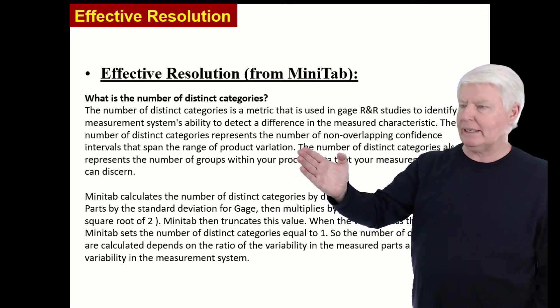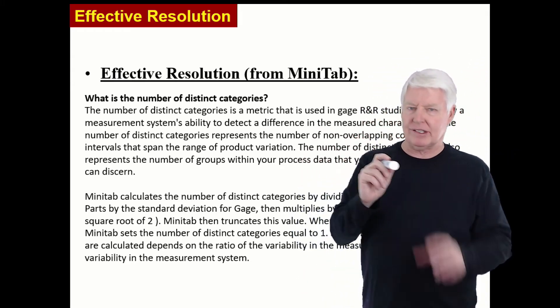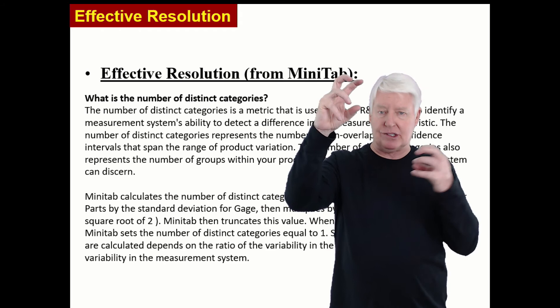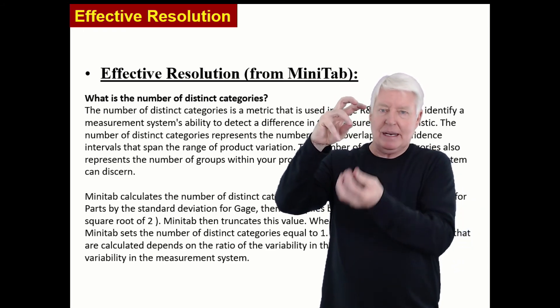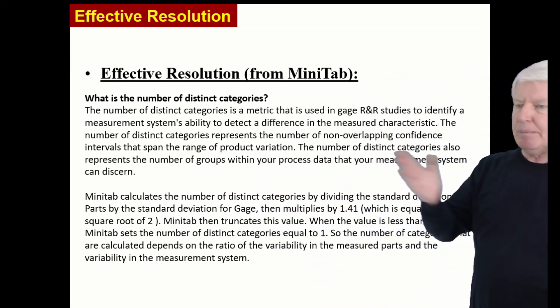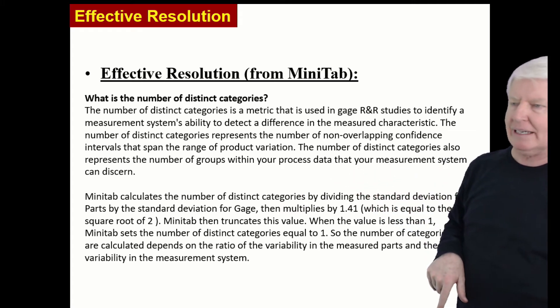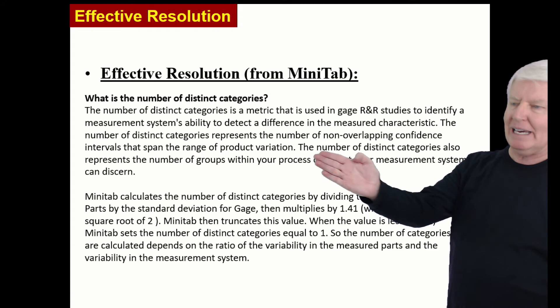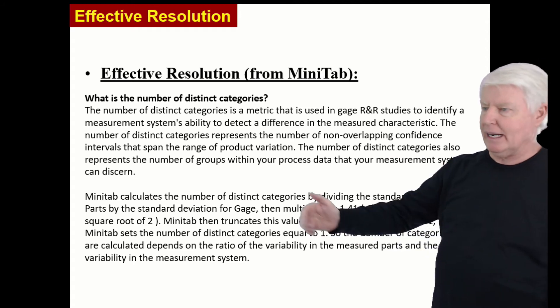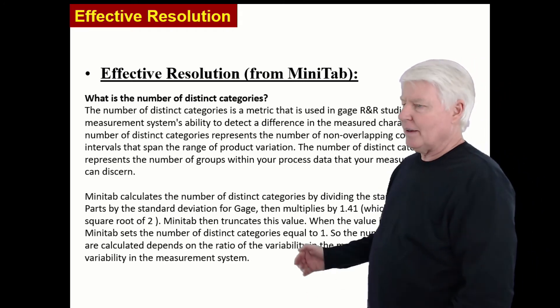The number of distinct categories represents the number of non-overlapping confidence intervals that spans the range of product variation. So what we're going to compare here is product variation. Remember, we had sigma of the parts, right? And then we had sigma of measurement. So they're comparing sigma of the parts to sigma of the measurements, seeing how many times the sigma of measurement fits into sigma parts. That's really what it's telling us here. The number of distinct categories also represents the number of groups within your process that your measurement system can discern. So that was my definition, number of columns on your histogram, number of distinct categories, columns on the histogram, also represents the number of groups within your process data that your measurement system can discern.